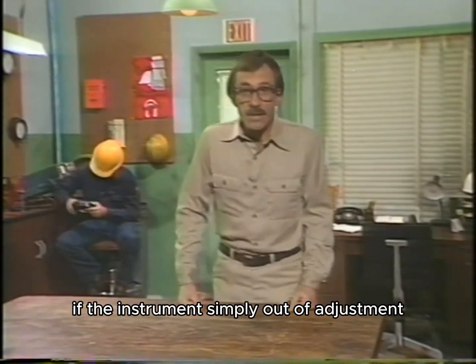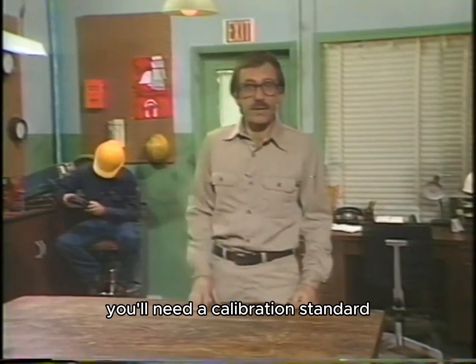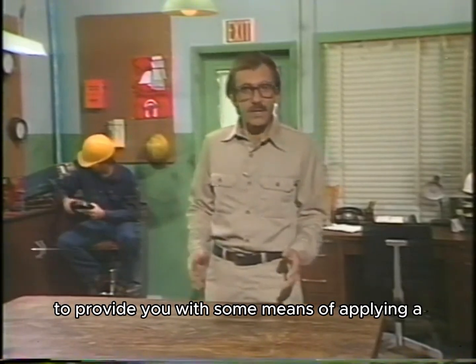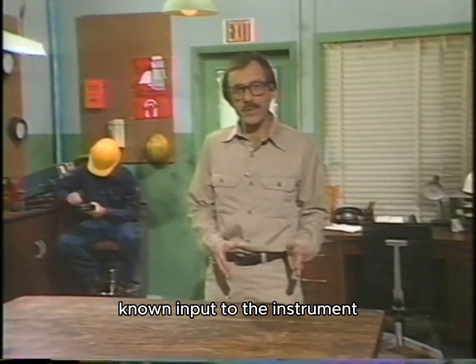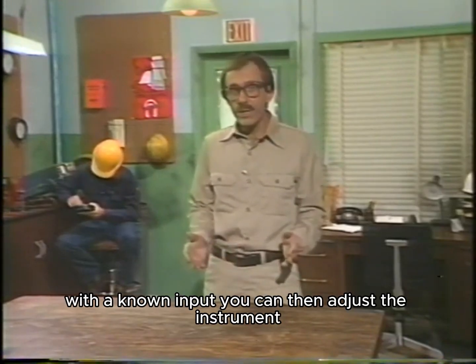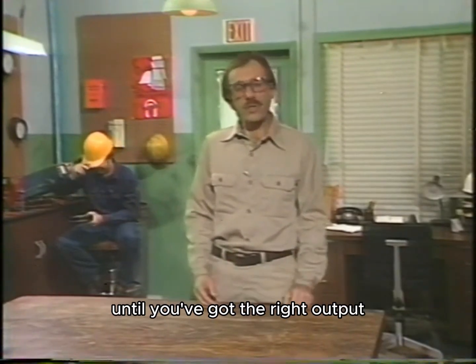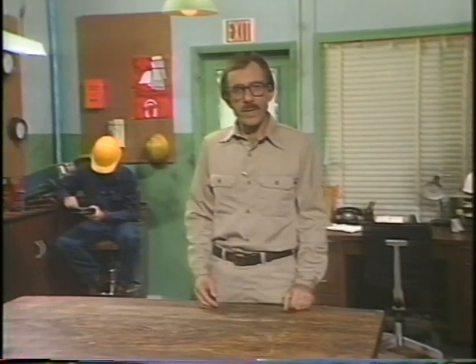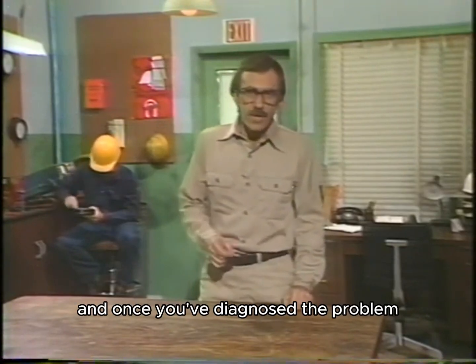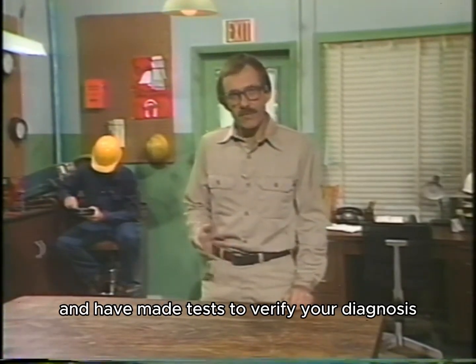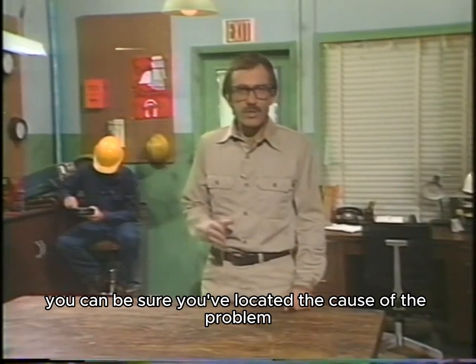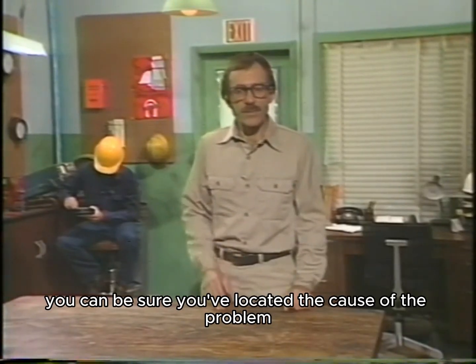If the instrument's simply out of adjustment, you'll need a calibration standard to provide you with some means of applying a known input to the instrument. Now, with a known input, you can then adjust the instrument until you've got the right output. Once you've diagnosed the problem and have made tests to verify your diagnosis, you can be sure you've located a cause of the problem.